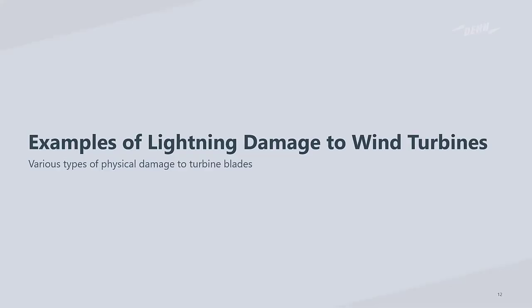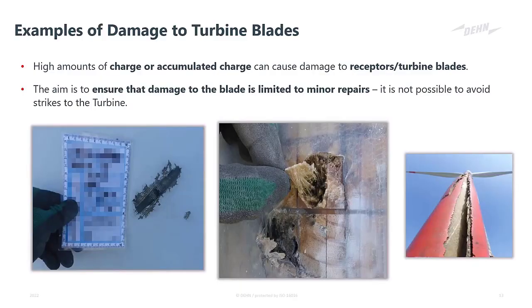Now, understanding that the peak value of lightning current and charge is a very large contributor to damage, we can also have a look at some examples of lightning damage to wind turbines. These first damages are smaller types of damage, except for maybe the one on the right, which is quite a lot of damage to a blade. But what happens is that high amounts of charge, or accumulated charge, can cause damage to the turbine blades or the receptors. We will speak about a lightning receptor in detail in a few slides as well. But a turbine blade contains what's known as a lightning receptor. And when there is a lightning strike onto a turbine blade, there's a concentration of charge at a single point.